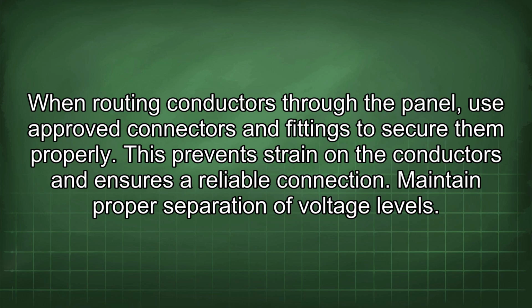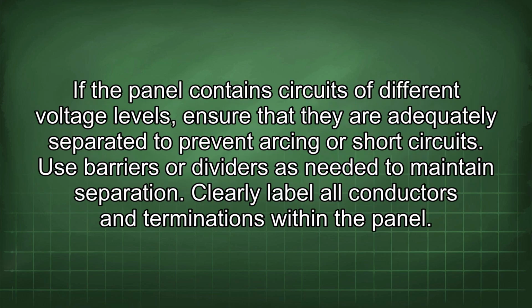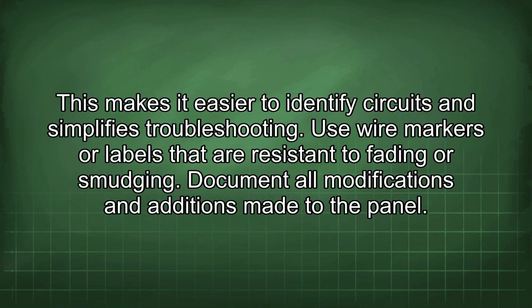Maintain proper separation of voltage levels. If the panel contains circuits of different voltage levels, ensure that they are adequately separated to prevent arcing or short circuits. Use barriers or dividers as needed to maintain separation. Clearly label all conductors and terminations within the panel. This makes it easier to identify circuits and simplifies troubleshooting. Use wire markers or labels that are resistant to fading or smudging.